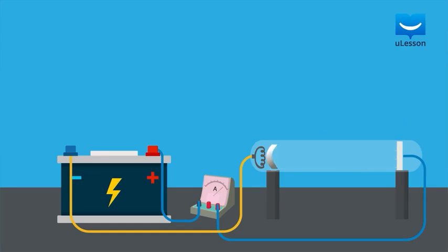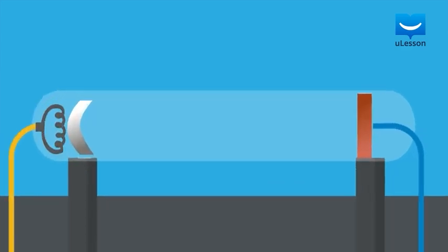The target plate is made of tungsten or titanium, but this is also embedded in a copper block to also serve as the anode. Copper has a high conductivity, so this helps to direct the heat and current better. Let's look closely at the tube before we move on.